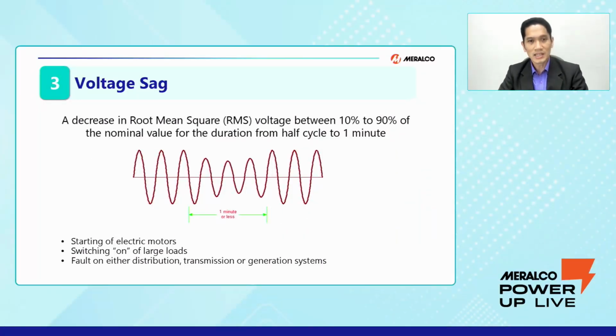And for the voltage sag, this is a decrease in the root mean square of the voltage between 10% to 90% of the nominal value for a duration of half cycle to 1 minute. So usually, we call this a voltage fluctuation, but the correct term is voltage sag. This is due mostly to the starting of electric motors or large loads, or there is a fault on either the distribution, transmission, or generation system.